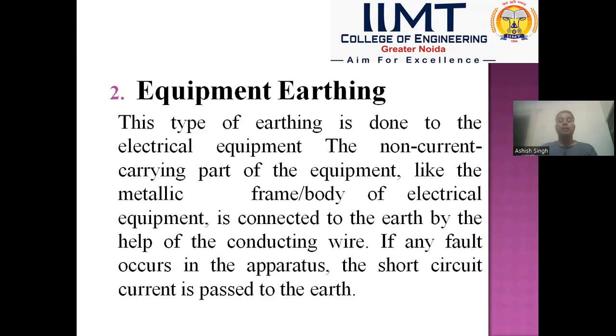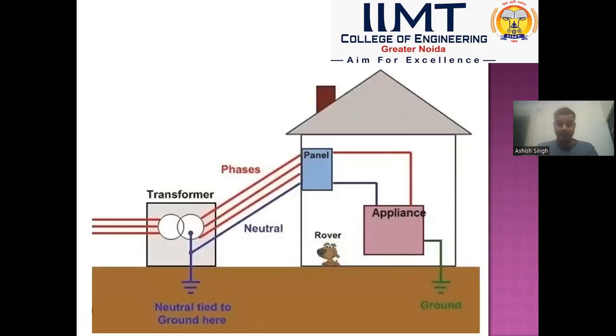If any fault occurs in the apparatus, the short circuit current is passed to the earth. Here, a pictorial representation is shown of system grounding as well as equipment earthing. We see here electric energy coming to the substation where a step down transformer is connected, and the primary side is delta connected and the secondary side of the transformer is star connected. On the secondary side where the star connected winding is there, a neutral wire is connected to the earth with the help of a short piece of wire.